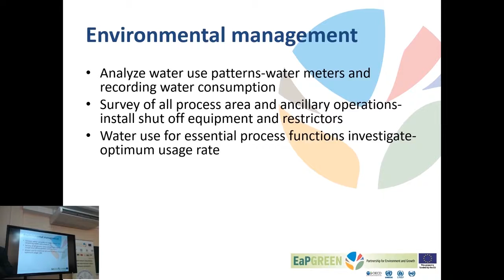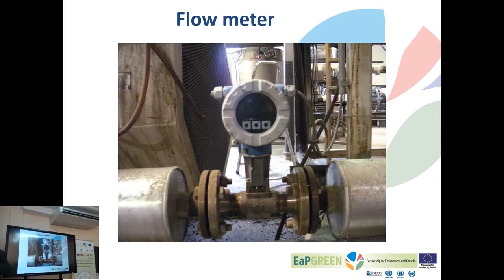So for the major equipment and for cleaning — maybe for the CIP cleaning plants, maybe for general cleaning — there should be dedicated meters. They can be very simple turbine meters read on a daily basis, or in a bigger plant nice automatic meters, but there should definitely be 3, 4, 5 sub-meters for water, to be able to attribute water consumption to individual units and individual areas.